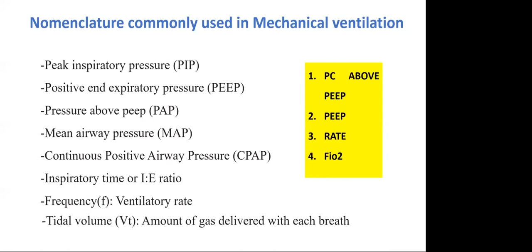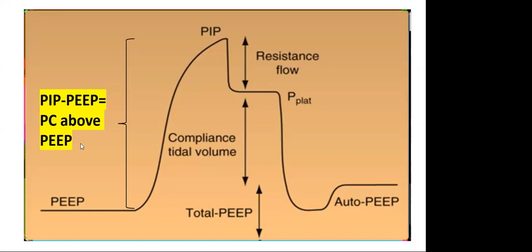And pressure control above PEEP. After that, the ventilator will deliver with a certain pressure. Okay, it has a limit. How much pressure it is giving, the maximum, that is your peak inspiratory pressure. The difference between your peak inspiratory pressure and your PEEP is your pressure control above PEEP, which is what you will see in Maquet and others. So PEEP is the pressure in the alveoli at the end of expiration, maintained to prevent the alveoli from de-recruitment. And then there is the pressure control above PEEP. Okay, that is the thing.